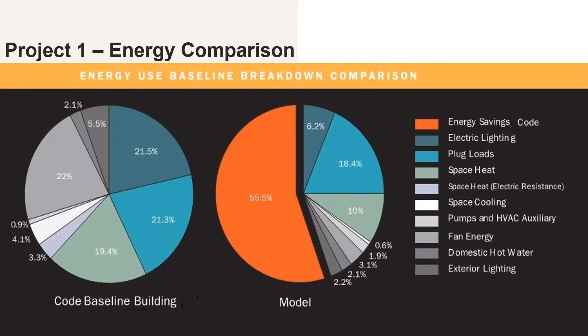And when you do that, you can't downsize the mechanical equipment unless you're able to address your peak criteria for the design day. That's why the envelope becomes so important, because you start reducing the requirements for heating and cooling on those peak days through your envelope. Here, the super-insulated envelope wasn't employed, but that was a learning lesson from ten years ago.